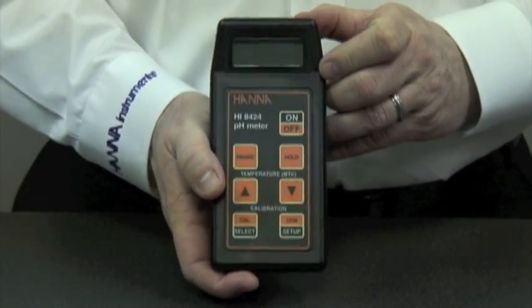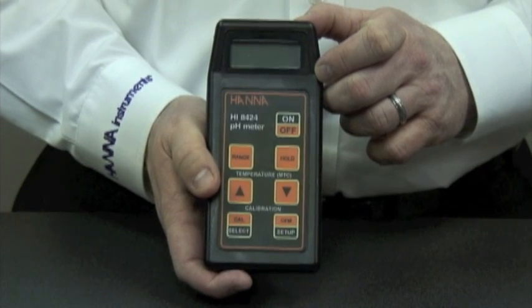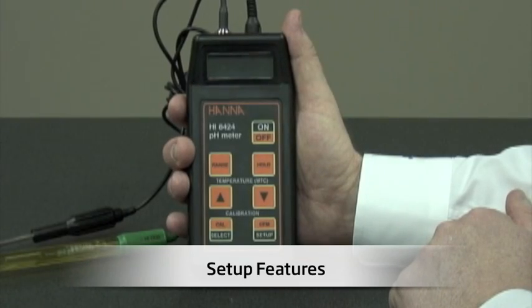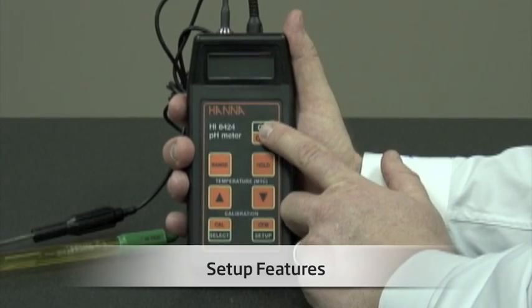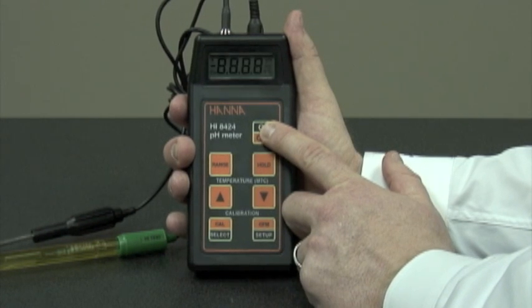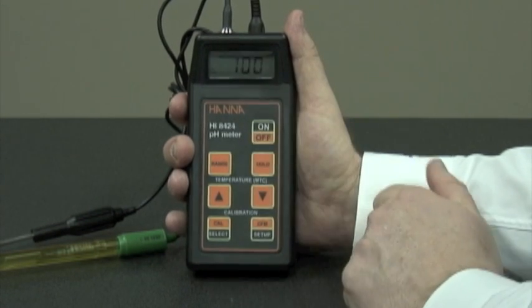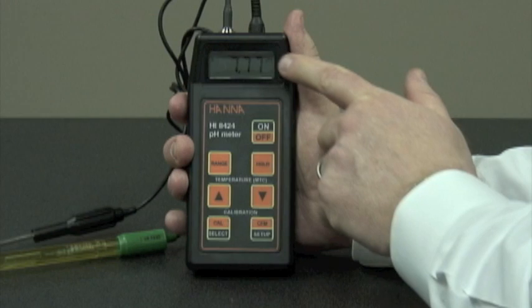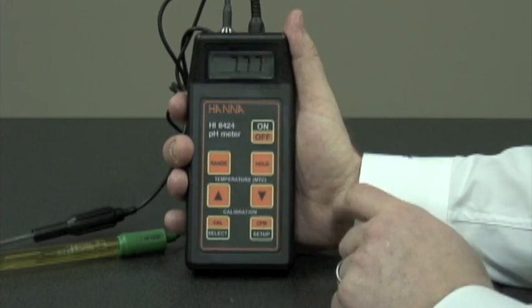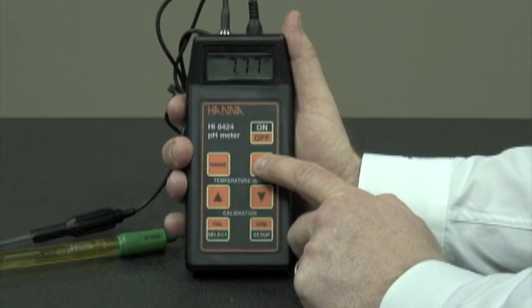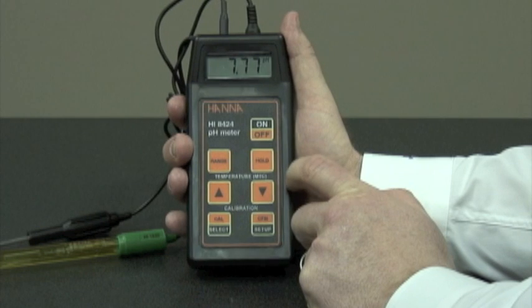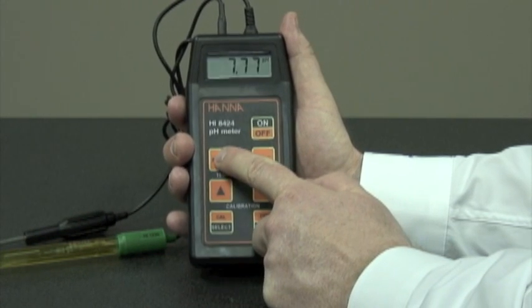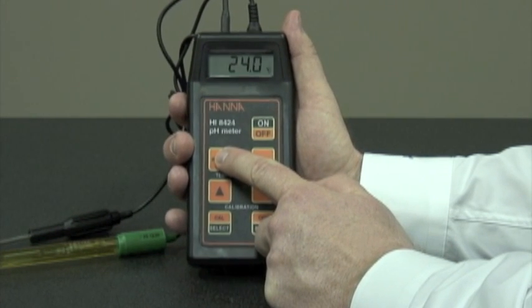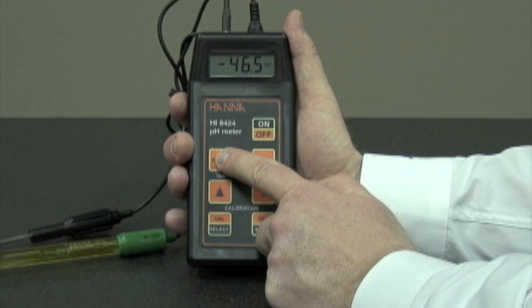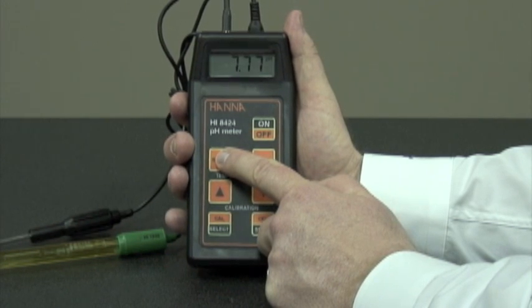Now we'll hook up the probes and turn the meter on. Now we've inserted the probes and we'll turn the meter on. Immediately you'll see the battery percentage level, and now the display is showing pH. We can use the hold button to hold the reading. We can use the range button to show temperature, millivolt, or back to pH.